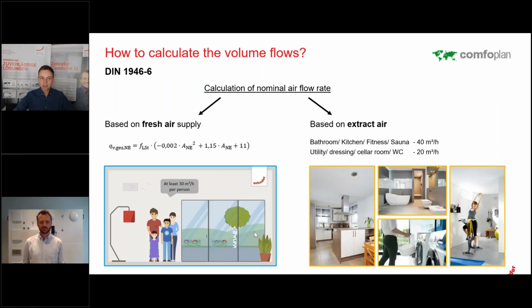But how are these volume flows calculated exactly? There are 2 different approaches. The one with the higher result is taken into account. So firstly, we can go with the required fresh air supply. As I already said, we calculate with 30 cubic meters per person per hour. The result is typically lower than the calculation based on the usable area. So this is the formula from the DIN, from the standard. So you have some factors and you need to set in the area and get out the volume flow in cubic meters per hour at the end.